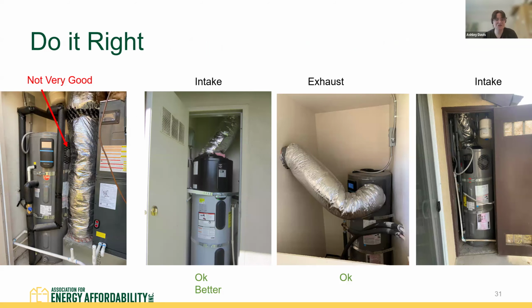So yeah, whatever ventilation strategy you choose, it's important to make sure it's done right. For example, on the left here is an example of not ducting at all, but you can see that that exhaust fan is almost completely covered by the adjacent HVAC duct. So if you're choosing not to use ductwork, you have to make sure there's unrestricted access to both the intake and the exhaust fans, or those grills, so that there's proper airflow through the unit.